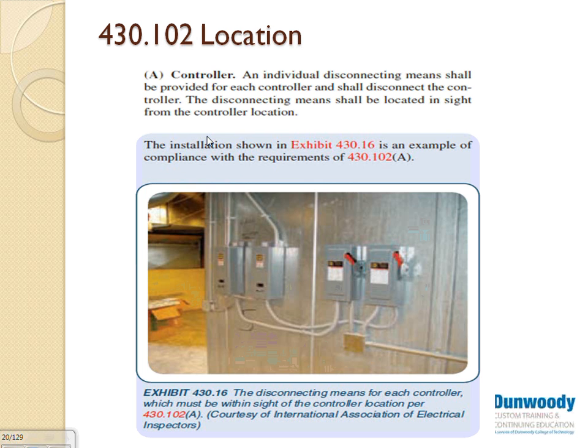That's another rule. The third rule is, if because of whatever reason, usually commercial, industrial, they allow you to have a disconnect that you can lock in the open position in one location like the MCC. So you can go lock it. It's not within sight of the machine or the equipment, lock it, tag it, and then you can work on the equipment. So there's a lot of rules for the disconnect, but the ideal situation is to have the disconnect right next to the machine. So you can disconnect the machine and work on it. For us, the mechanicals, everybody else.